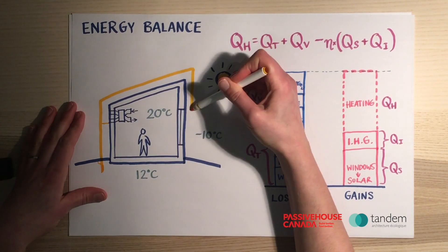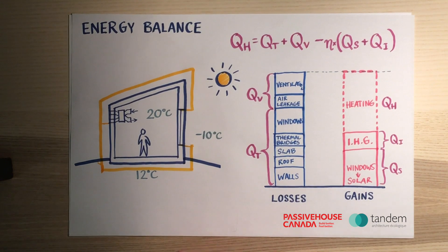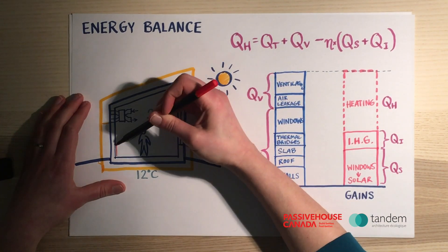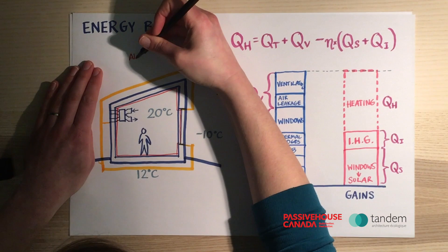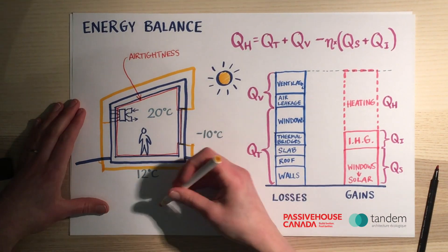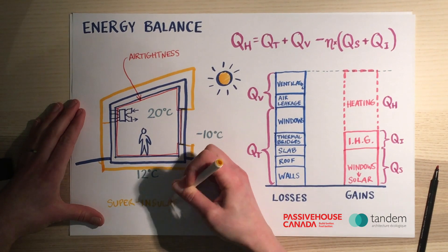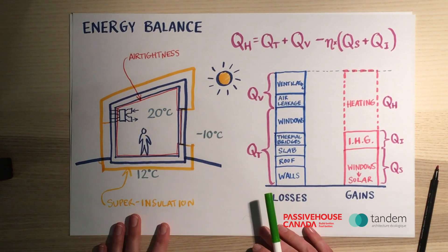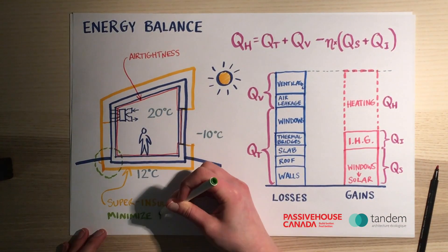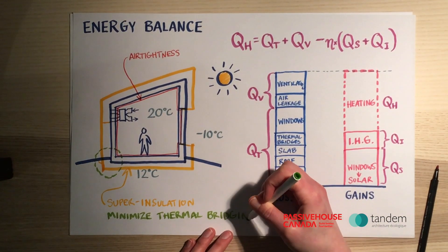There are a number of things we can do to improve our building performance. The first is to add insulation — we're going to reduce our losses through the walls, roof, and slab by improving the insulation value and by making sure that our envelopes are very airtight, which will reduce our air leakage. Then we'll minimize thermal bridges by looking at all of our details and optimizing them for airtightness.